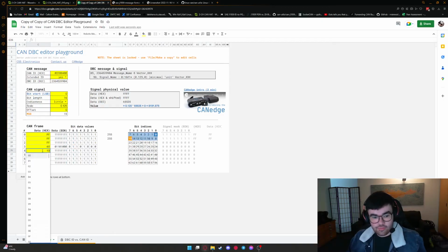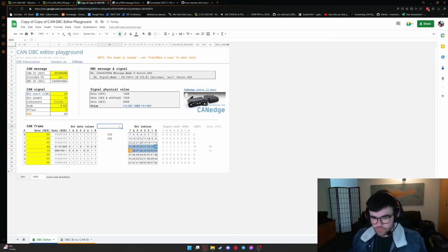Okay, and after that's 13. Put that in there in slot number 4 or 5. And the rest are just F, and they're already F here, so that's fine. So now we pick our bit start. This will change depending on the device. And you might have just all Fs, right? Just all Fs, but the bit start is still set specifically for this CAN ID. We know that this starts at bit number 24. So we put in here bit start, least significant bit of 24. Our bit length is 16, which is 2 bytes. It's already 2 bytes long, but if it were 3, we would increase that to 24, but we don't need to now, so that's fine.